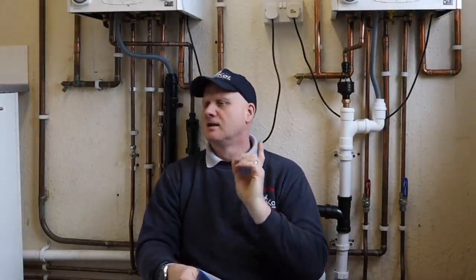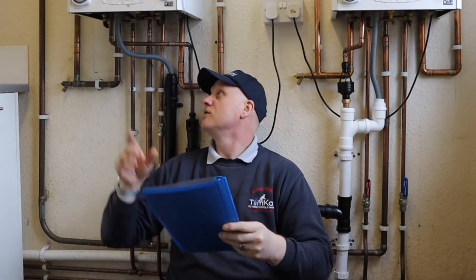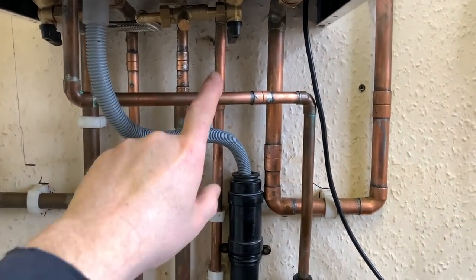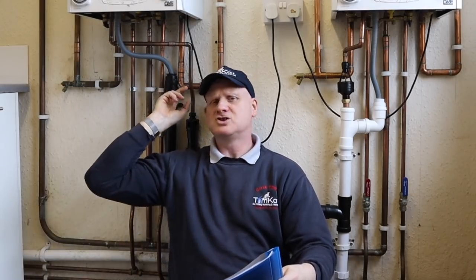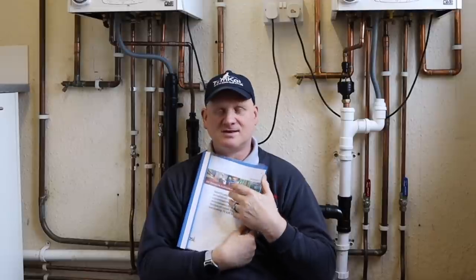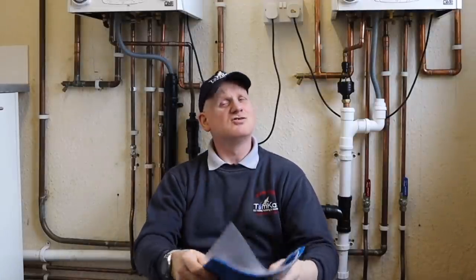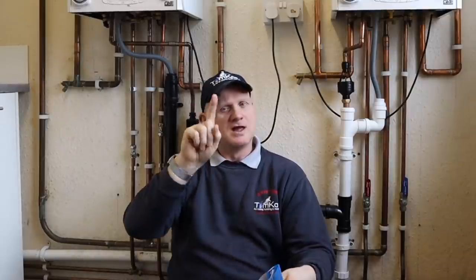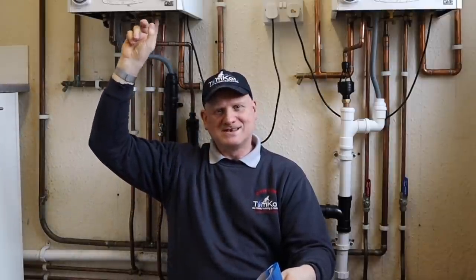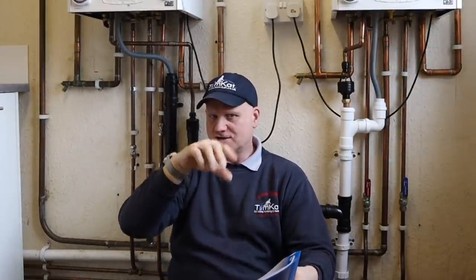Now, it's becoming pretty common now that engineers are installing their condensate pipe with their pressure relief valve in the same system. Instead of taking the pressure relief valve outside, they're discharging it into the same pipe. And BS6798 doesn't really say much about it. It just basically says there's two ways of doing it. There's one way which is actually done by the manufacturers inside the boiler, and I know Viessmann do this, where they combine the blow off and the condensate inside the boiler. I can't think of any other manufacturers that do it, but if you do know them, put them down at the bottom in the comments.